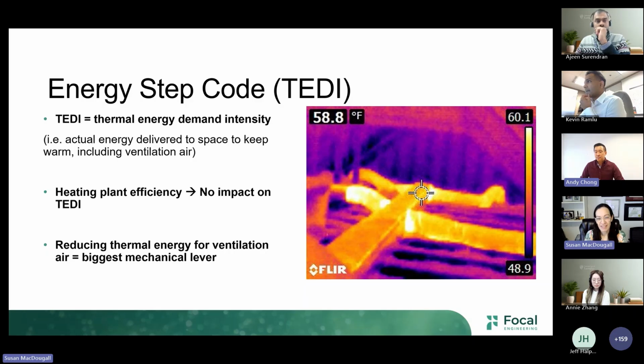Yeah, can I jump in on that one? We've seen that a lot on low rise, especially because you're not running as much ductwork as you would for a high rise. We've had projects that looked at smaller HRVs for each corridor, when the corridor isn't just a central one but has some exterior wall somewhere. So there's just a small HRV going through the corridor at each level, providing ventilation and a little pressurization. That was definitely an area of study we were looking at, trying to reduce the heat loss. The step code is still a bit unusual because it allows the corridor adjustment for pressurization, so it skews the results a little when the adjustment is applied. It makes it very building-specific based on the CFM per door being used.